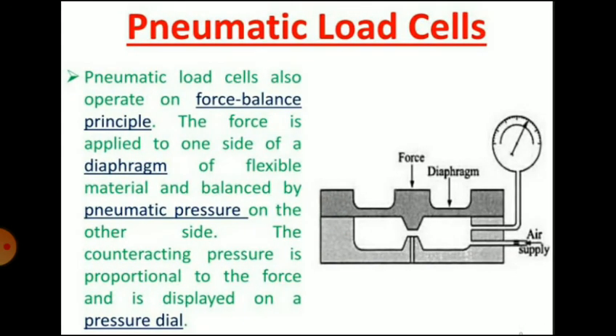Now, the next type is pneumatic load cells. Pneumatic load cells also operate on the force balance principle. The force is applied to one side of a diaphragm of flexible material and balanced by pneumatic pressure on the other side. The counteracting pressure is proportional to the force and is displayed on a pressure gauge. You can see the diagram of the pneumatic load cell.